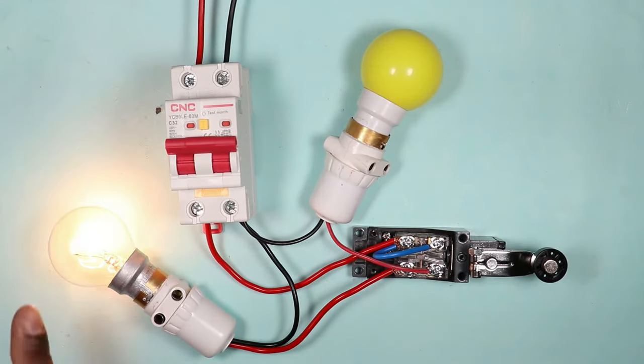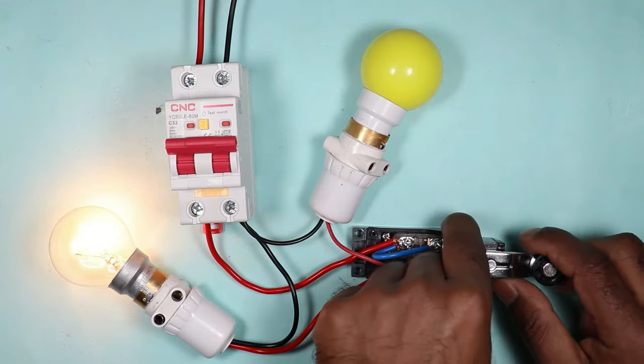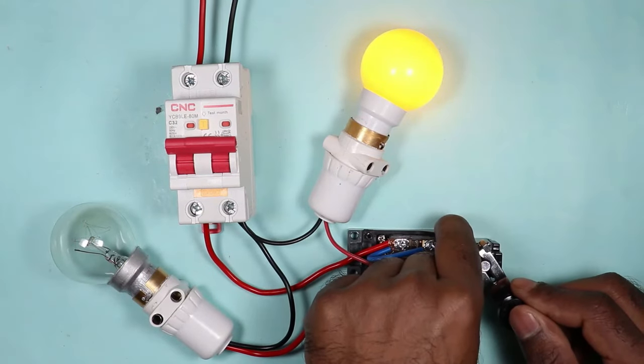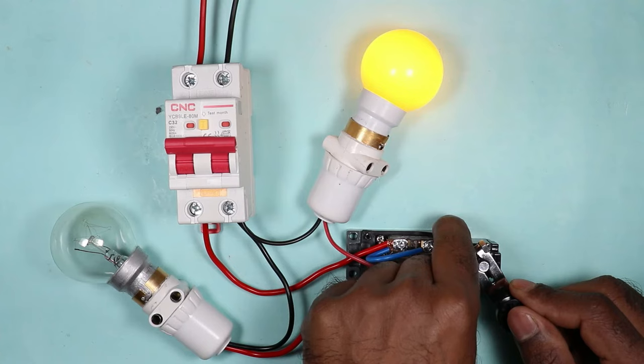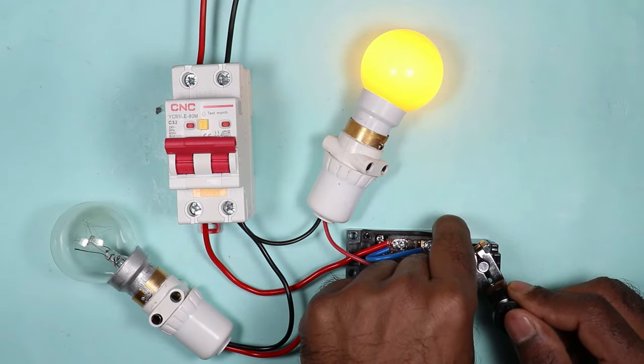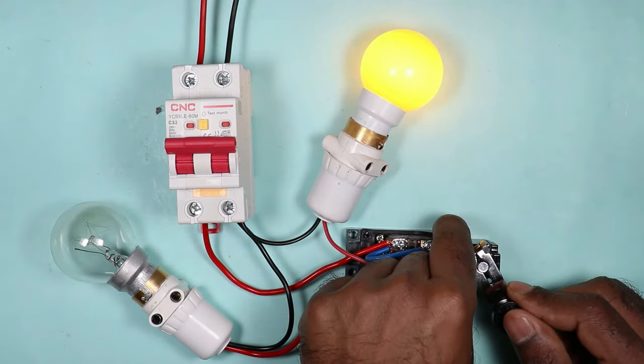On turning on the MCB, you can see this lamp is on now. This lamp was connected with NC contact, so it is turned on. Now if I operate this limit switch, then you can see lamp connected with NC is turned off and with NO turned on. This means, now limit switch is generating output signal to NO contact and stopped signal to NC contact.